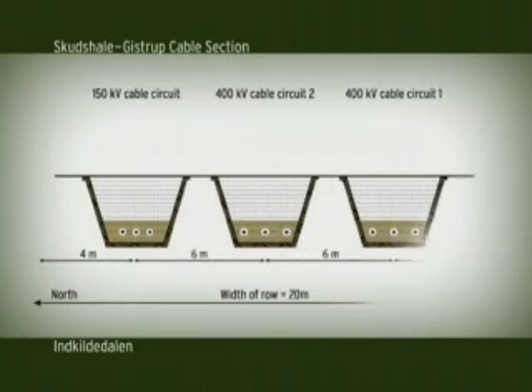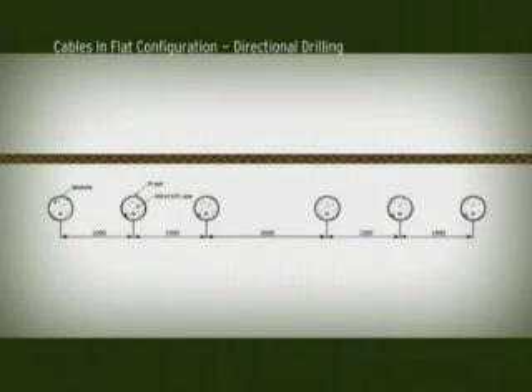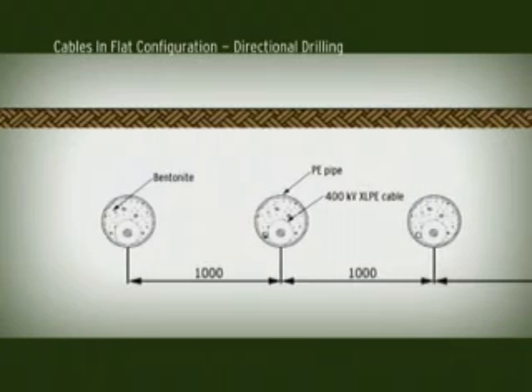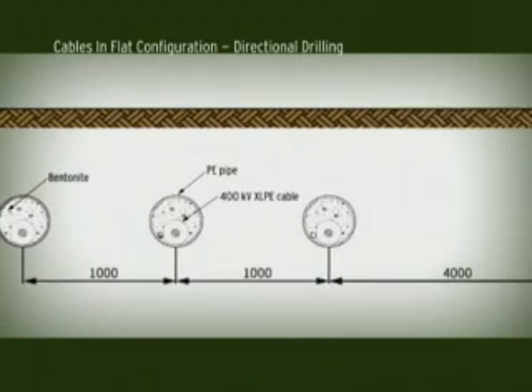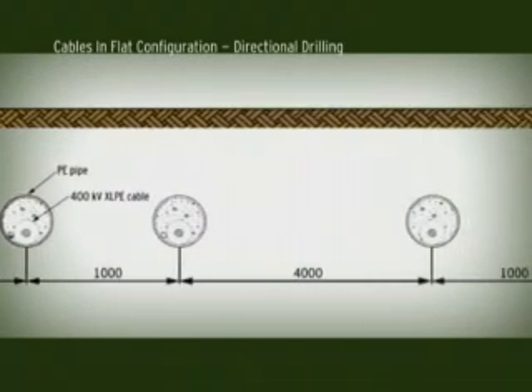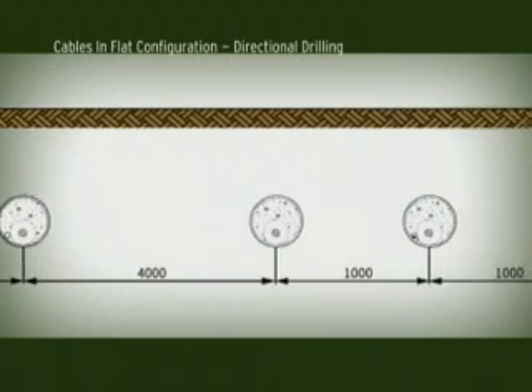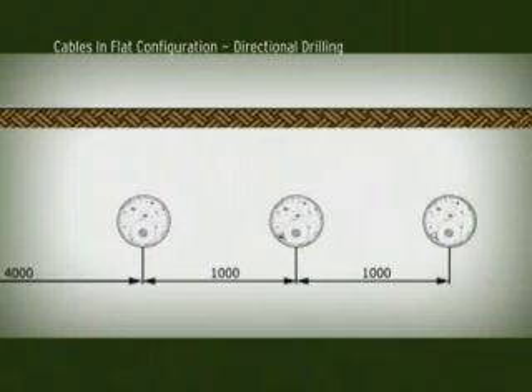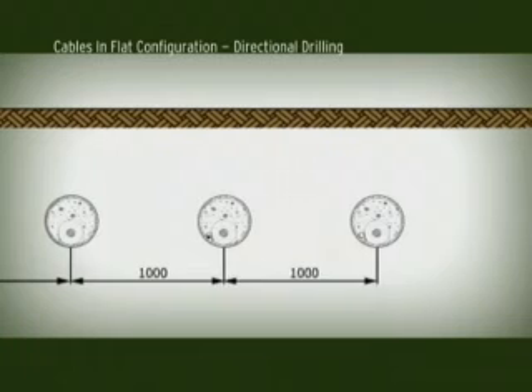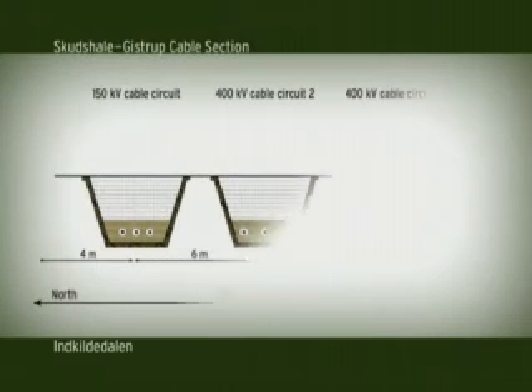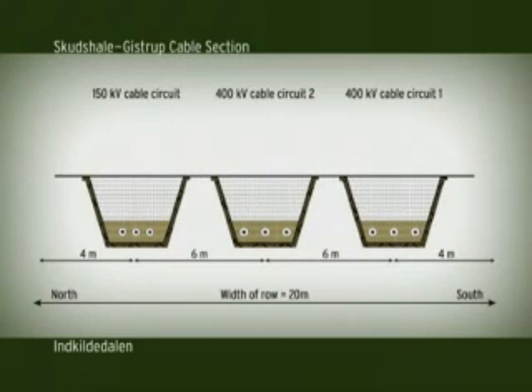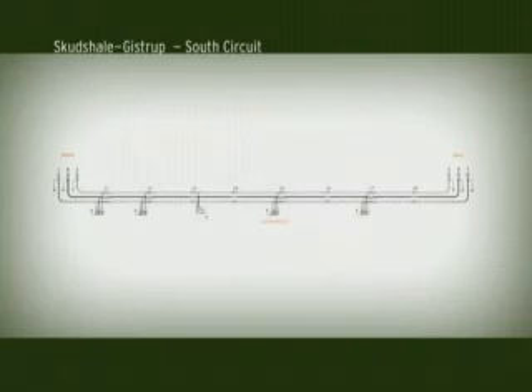The cables lie in a flat configuration along the entire section. All directional drillings beneath roads, rivers and other transverse lines are also performed as flat configurations. Along this section, one pipe has been pulled through each directional drilling. In the deep directional drillings, the cables have been pulled so they sit so far apart from each other that they can release the heat emitted during heavy current loads more effectively. The cable shields are cross-bonded. The phases have not been similarly crossed.